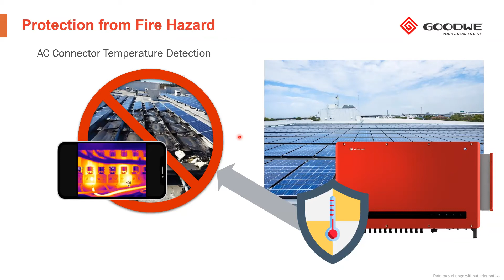If we can monitor the PV system at that level, we get more information remotely about how our system performs, including the protection level. This option is AC connector temperature detection, which controls the temperature of the connectors on the AC side, since sometimes the torque isn't properly done, etc. This helps us avoid future issues like what we see in the picture, which is why we keep it—to remember the potential effects of not properly attending to the operation of the PV plant.